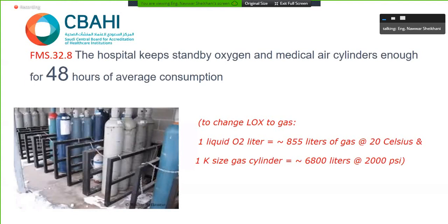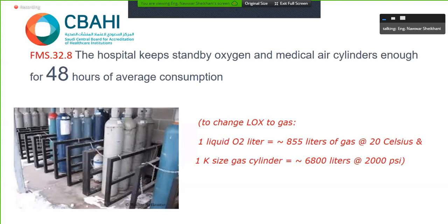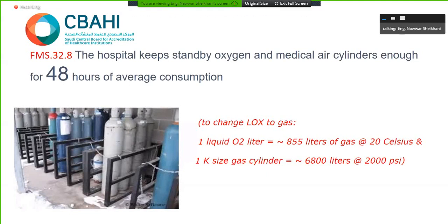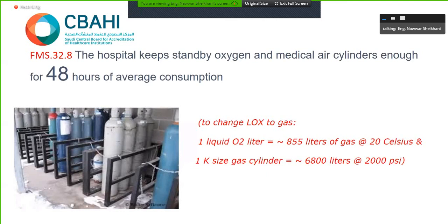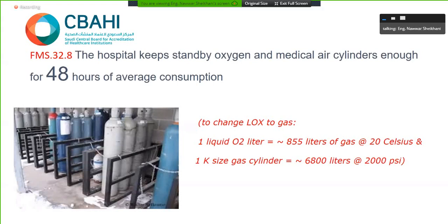Please consider that 1 liter of liquid oxygen is equal to 855 liters of gas at 20 degrees Celsius. And 1 K-size cylinder, the K-type, is equal to 6,800 liters of oxygen at 2,000 psi, pounds per square inch. So if you have a LOX system or K-size cylinders, you can calculate it. At the end, we have to see a signed document showing the average oxygen consumption in liters of gas in the hospital, compared with the cylinders you have. It should be a minimum of 48 hours.